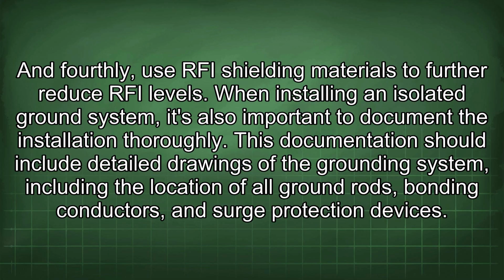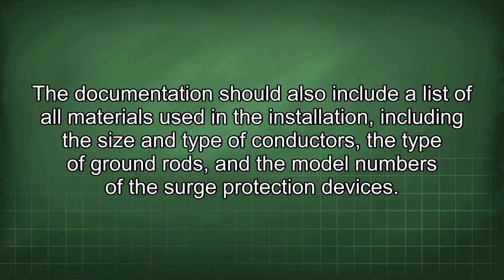When installing an isolated ground system, it's also important to document the installation thoroughly. This documentation should include detailed drawings of the grounding system, including the location of all ground rods, bonding conductors, and surge protection devices. The documentation should also include a list of all materials used in the installation, including the size and type of conductors, the type of ground rods, and the model numbers of the surge protection devices.